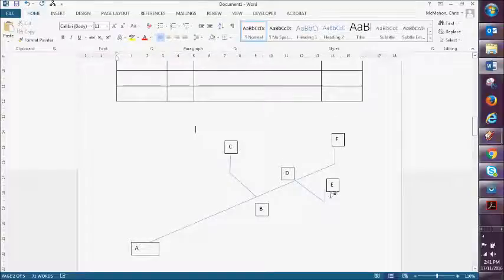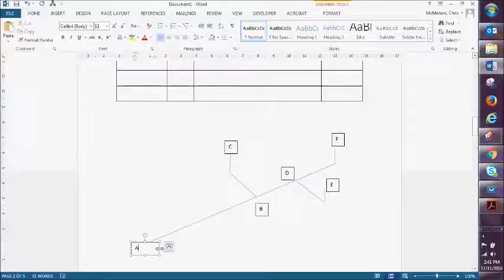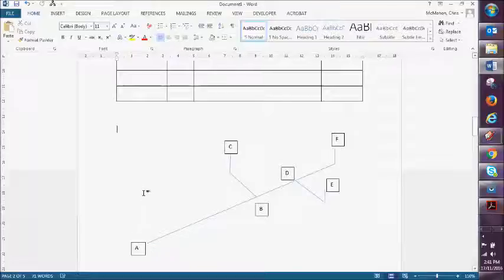Okay, so we'll say for this scenario, our furthest most appliance away from the meter is 32 metres away. 32 metre main. When we're talking main run, we're only talking about from the meter to the furthest away appliance. Yeah. So A to F is the main run.